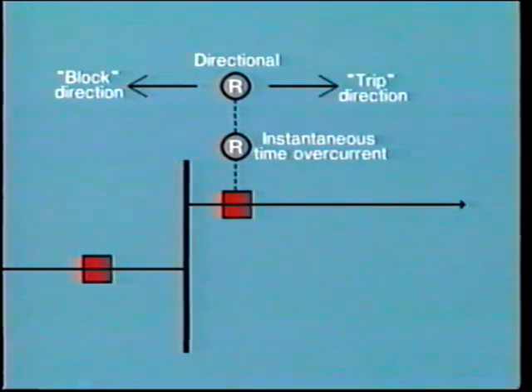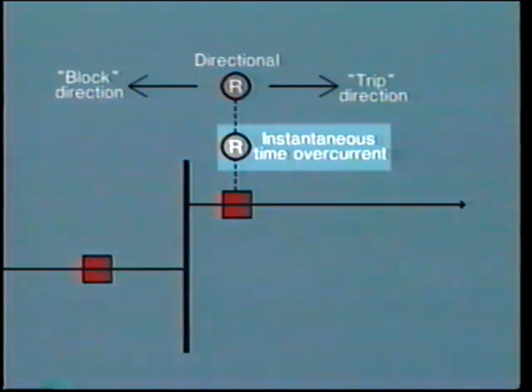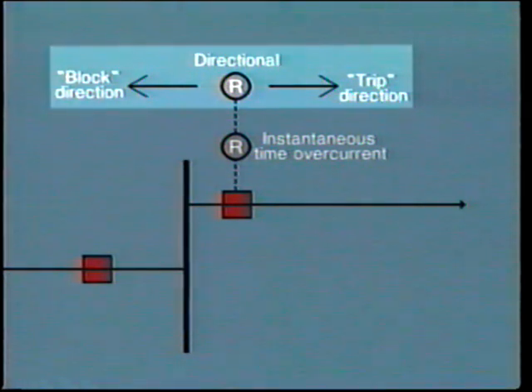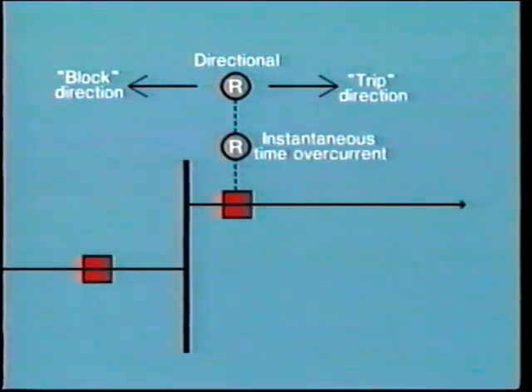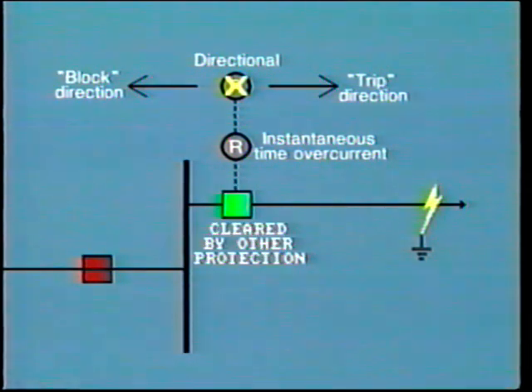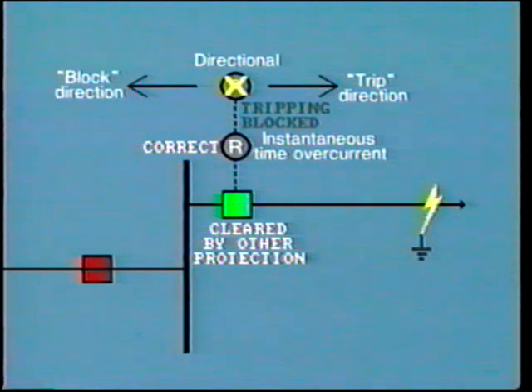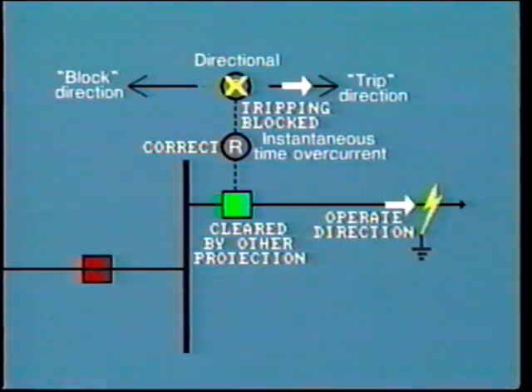The ground fault protection on this line consists of an instantaneous time overcurrent relay supervised by a directional unit. When a heavy ground fault occurred on one phase of this transmission line, the directional ground overcurrent protection failed to operate. The fault was actually cleared by other protection. Subsequent checking of this scheme showed that the instantaneous relay picked up correctly, but tripping was blocked by the directional unit even though the current was in the operate direction.